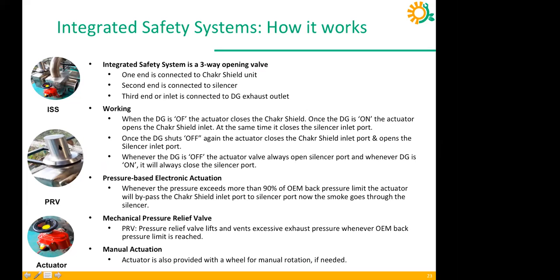Then we have a PRV system installed that will simply open up at 6.77 kPa, and then the exhaust will start flowing outside. And we have provided a manual override, so any person in charge on site who maintains the DG can simply come and manually override the valves. That means opening the silencer route and closing our route, therefore ensuring in any scenario, if the back pressure is coming to 6.7 kPa, the safety system will start working and the DG will never suffer a downtime in any scenario.